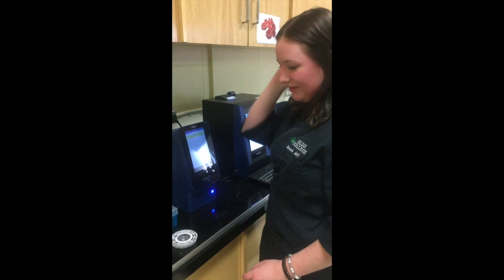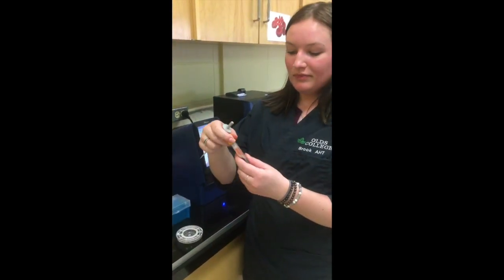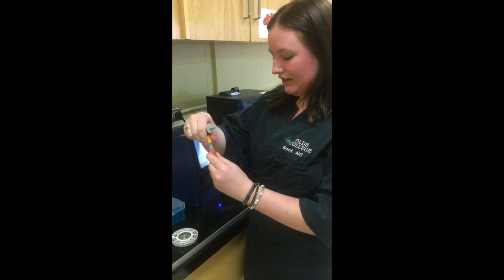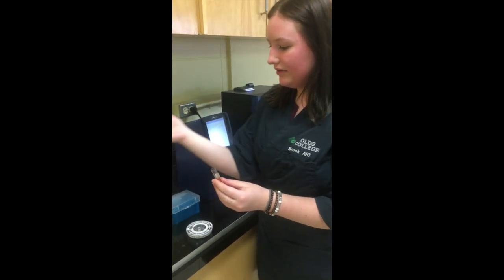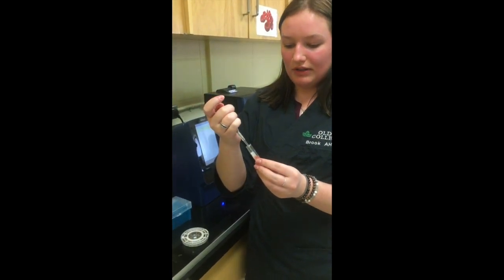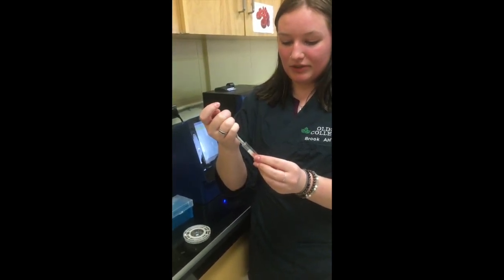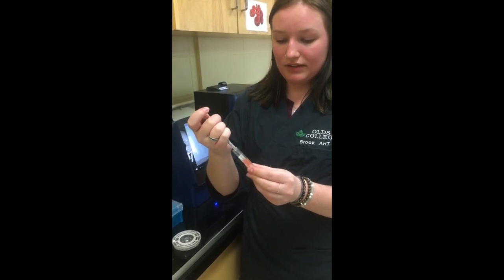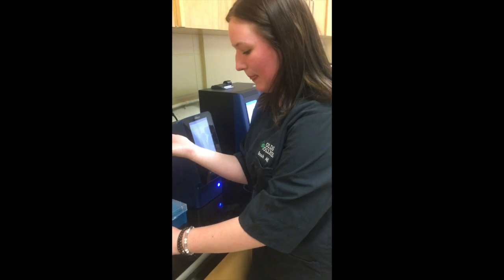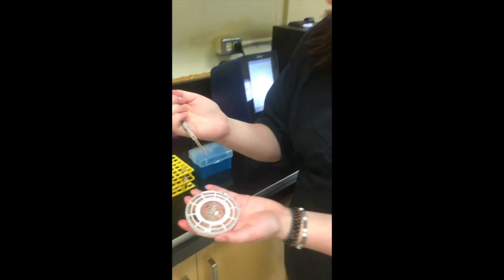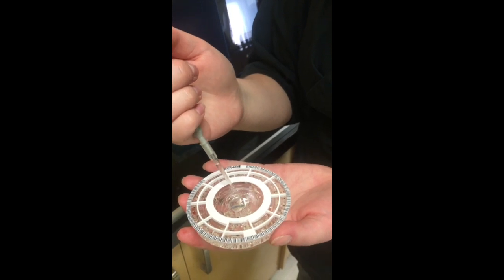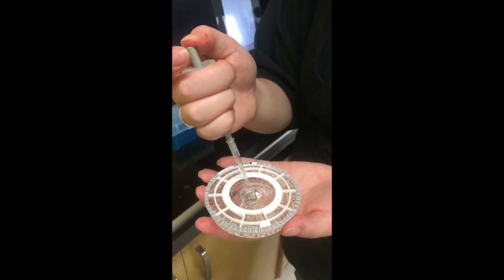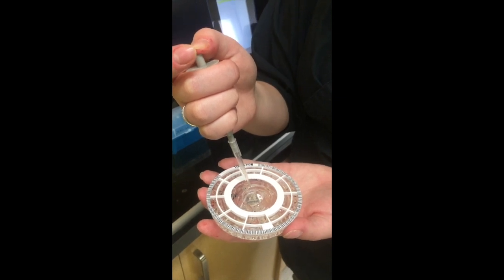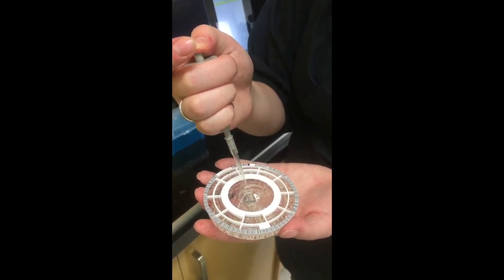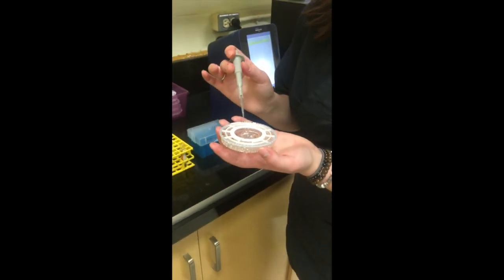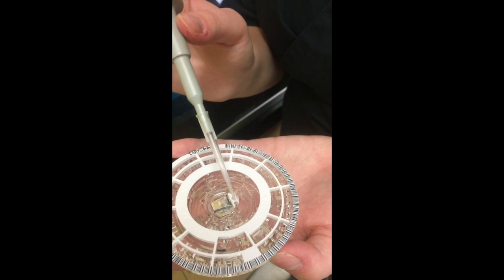I'm running the VET scan machine. And I'm going to have my sample with the serum. Take the top off. And the pipette will bring out the exact amount I need. So I'm going to put it in and be careful not to touch the wax plug. And then on my disc, I'm going to put this in the hole with the arrow. And that should fill to this line between the 2 arrows on that side.